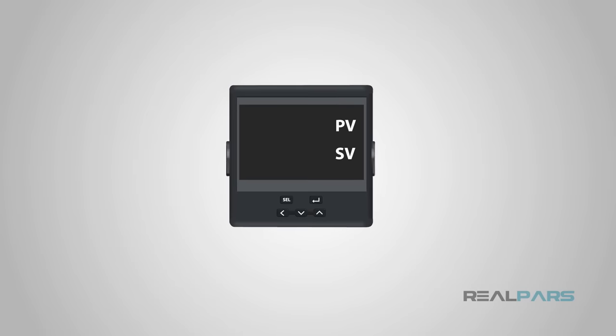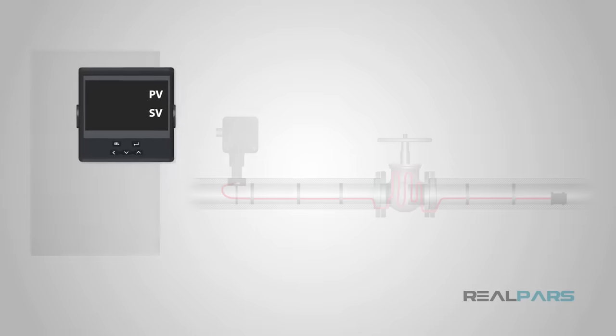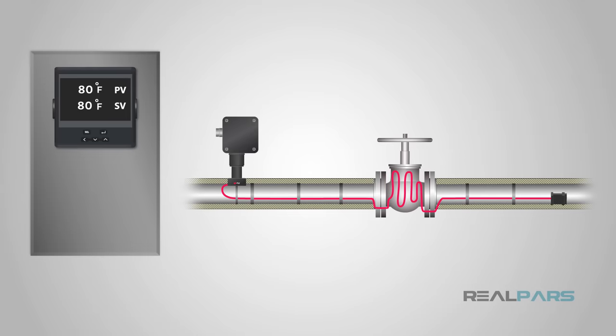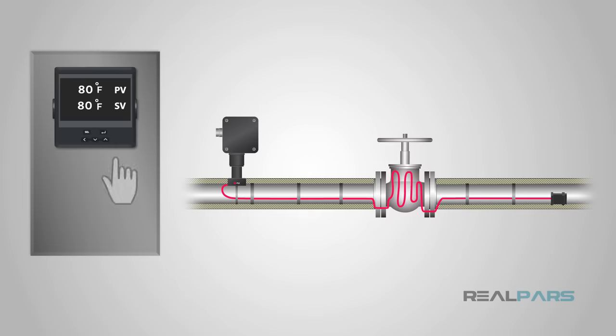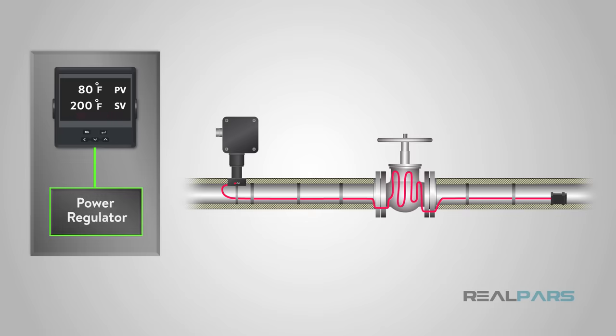For our example, we will look at a PID controller that controls the temperature of heat tracing on process piping. First, we need to enter a set point, 200 degrees Fahrenheit for our example. Now, the controller will give a signal to the output to start heating up the heat tracing.